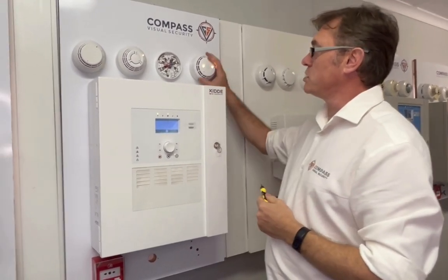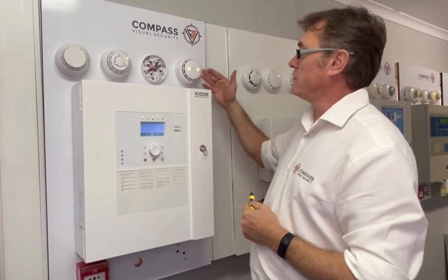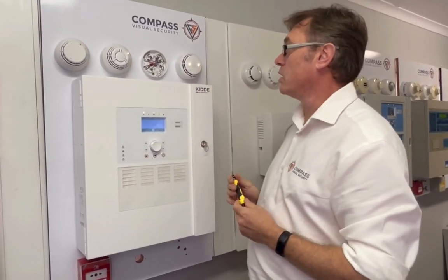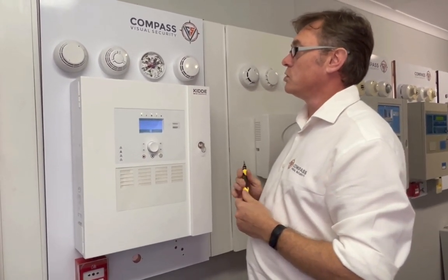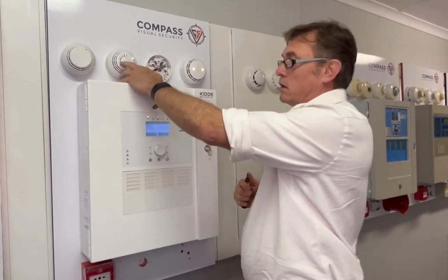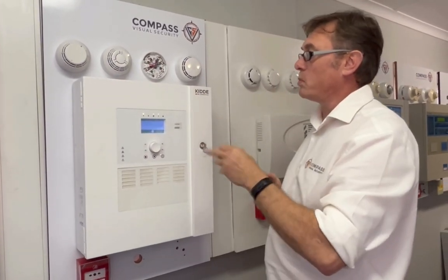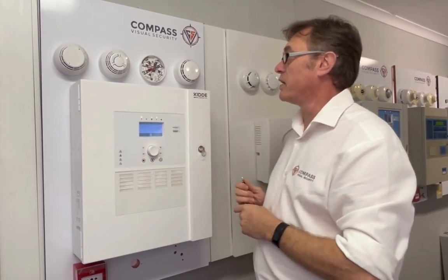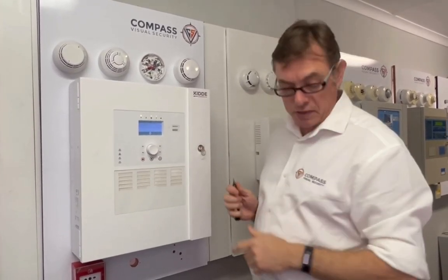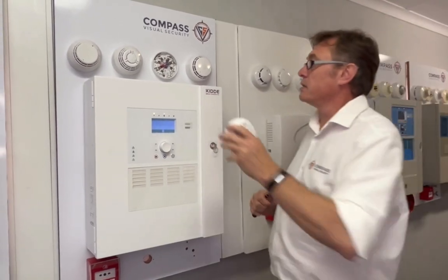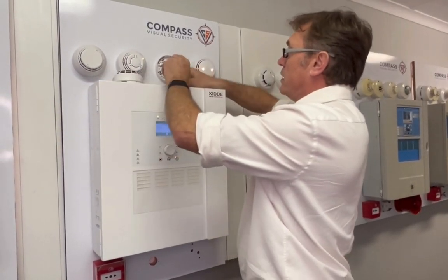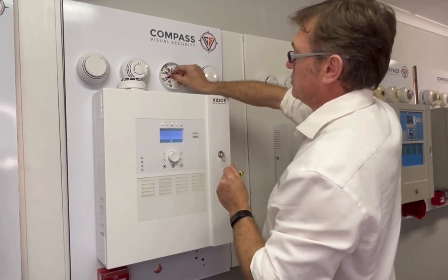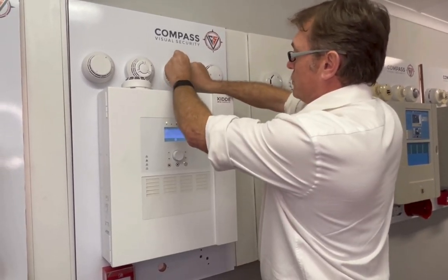And the nice thing with these new detectors, you can visually see if they have gone into isolation just by the solid yellow. If there's a fault, normally you would see a flashing yellow. Obviously if it's in pre-alarm, it'll be flashing red, and if it's permanent red, then it's in proper fire condition. Obviously when you initially plug them in, it'll flash green to mean that there's power there, which is also quite useful so that you know that there's power on the loop.